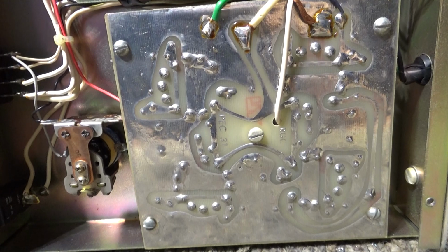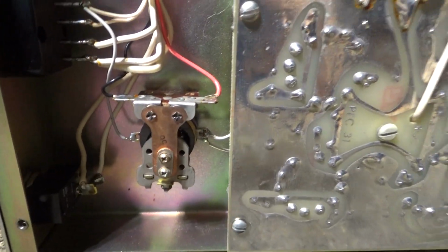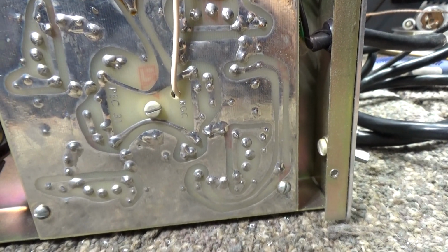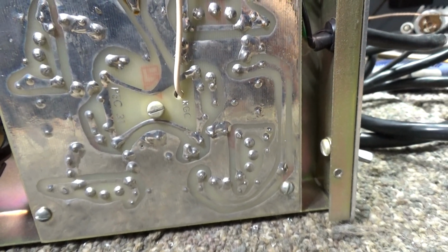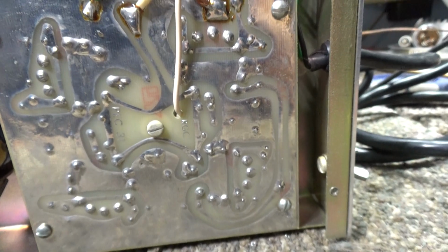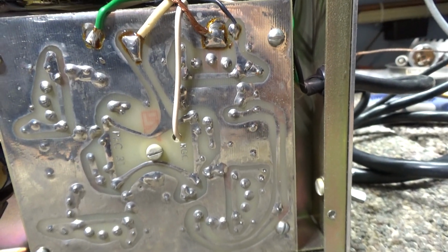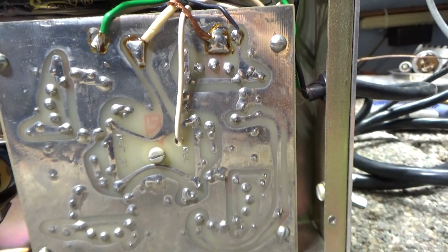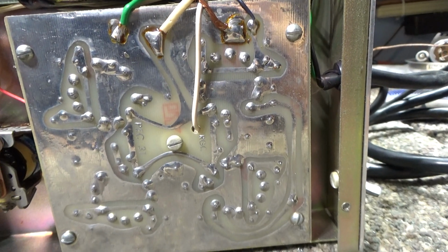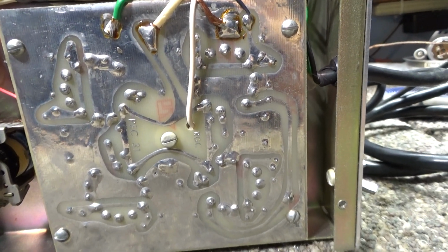Earlier Palomars didn't have that relay, so they had the high voltage going across into the tubes at all times. So you could leave it up in standby, and if one of those tubes arced or something funky happened, the amplifier could go up in smoke even in standby.